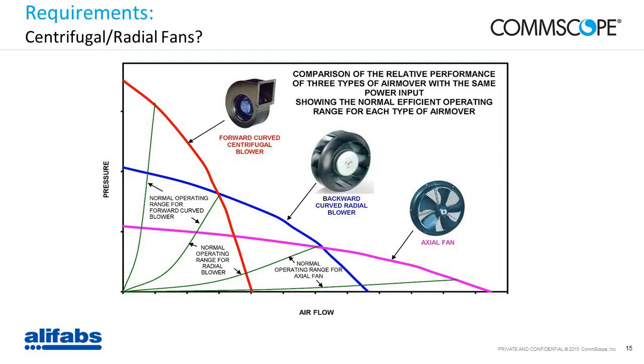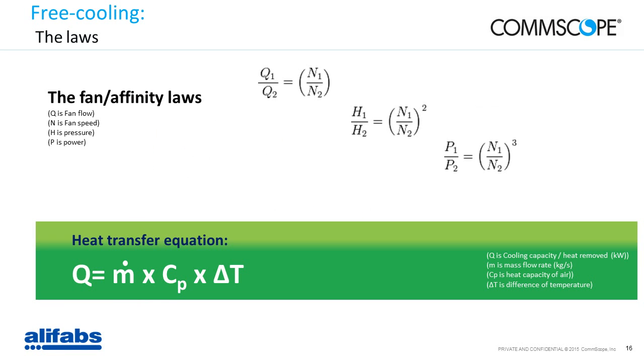So I will take you through something that may be very familiar for some of you, and a bit strange for others. But essentially, the free cooling laws are pretty simple. The fan affinity law says that if we increase the fan speed, we increase the fan airflow and obviously the cooling capacity. The relation between the fan speed and the pressure is a square relation. So if we double the speed and the airflow, we quadruple the pressure.